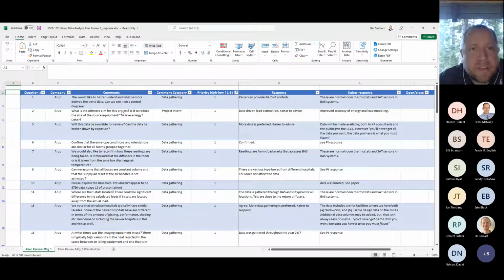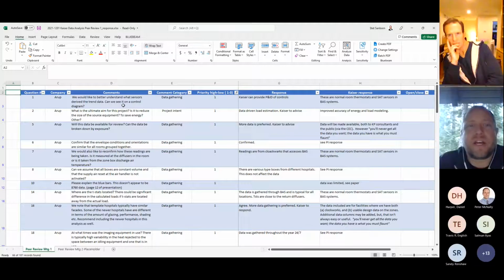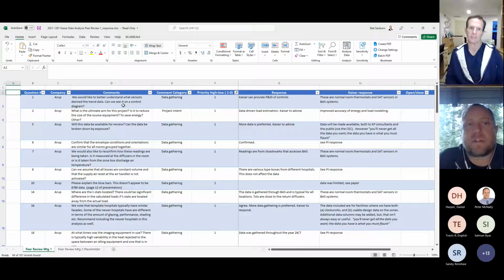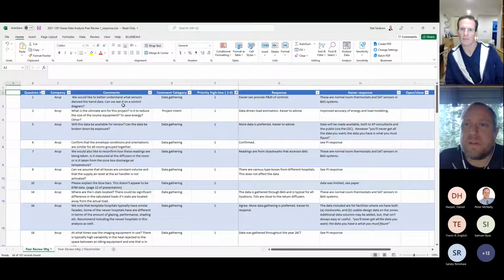But Bill, I think your team came back asking which sensors we were using. So we can certainly share the controls diagram, but effectively the sensors that we're using are the supply air temperature sensor at the tail end of each box. We're using the room thermostat, and then we're also doing the CFM that's being measured at the box. So we have airflow, and we have our delta T between the supply air temperature and the room measured temperature. We also had a few other temperatures that we have access to that we've pulled down, and that includes set point.